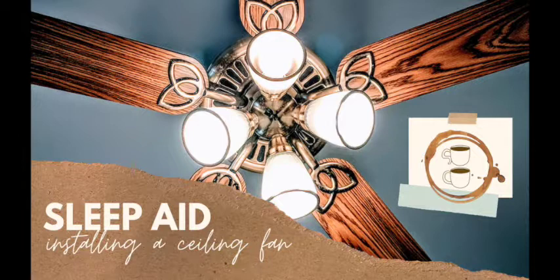Warning, make sure no bare wire or wire strands are visible after making connections. Place bare/green and white connections on opposite side of box from the black and blue, if applicable, connections. Turn spliced/taped wires upward and gently push wires and wire connectors into outlet box.